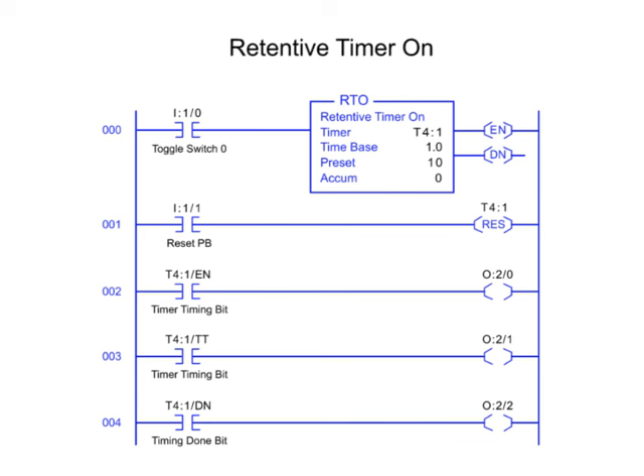The retentive timer on is enabled and begins timing when the input conditions are true. By changing the rung condition to false in the retentive timer circuit, the accumulated value stops timing and retains the time recorded until the rung condition goes true again. As the accumulated value reaches the preset value, the done bit goes true and enables the output.